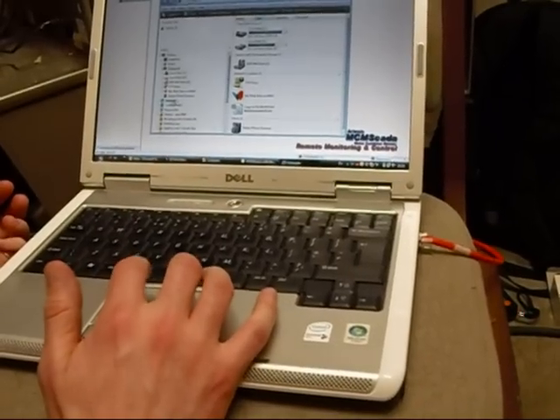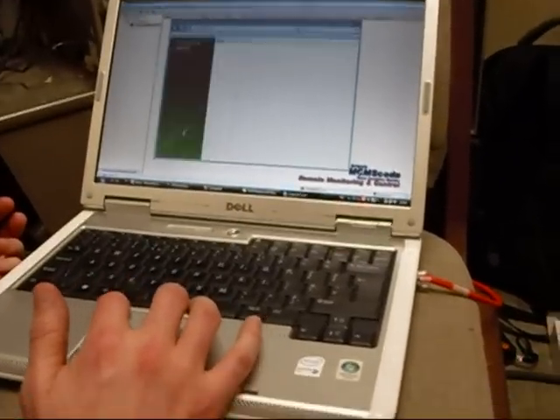What we're going to do, we're going to go in Control Panel, Network and Sharing. We're going to go into Manage Network Connections, and we're going to change our IP settings. So the default IP of this Moxa unit is 192.168.1.150. We're going to change the IP of the computer to be one digit away from this. So 192.168.1.149. We're going to be on the same subnet mask. We're going to click OK.